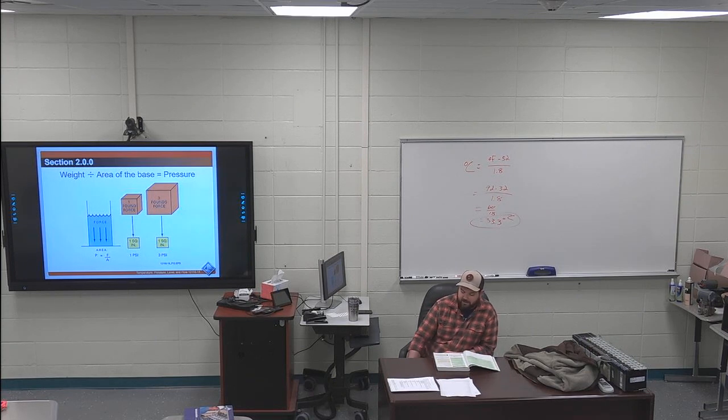I have the blue highlighted gauge pressure through the end of that paragraph highlighted. Gauge pressure is measured and expressed as pounds per square inch gauge, or PSIG, or kilopascals gauge, kPa gauge, and considers the presence of atmospheric pressure. For gauge pressure, the starting point of 0 PSIG actually begins at atmospheric pressure level. My next highlight is that next equation. PSIA is equal to PSIG plus atmospheric pressure. So absolute pressure is equal to gauge pressure plus atmospheric pressure.